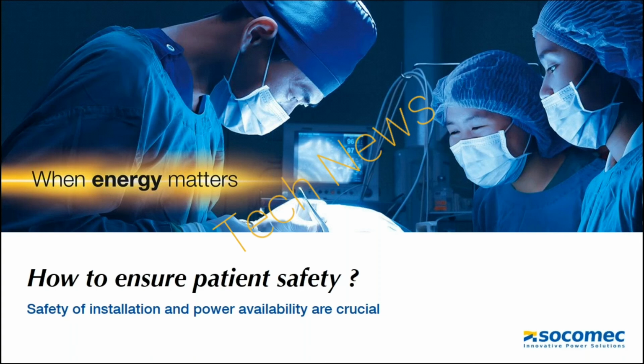Body functions are temporarily or continuously substituted by medical electrical devices. Ventilators would be a good example nowadays. And also fire and explosion risks through the use of anesthetics, disinfectants, or cleaning solutions. Many of these risks are the consequences of an insulation fault. So therefore, we need to ensure the risk of an insulation fault is removed in the context of these critical locations.